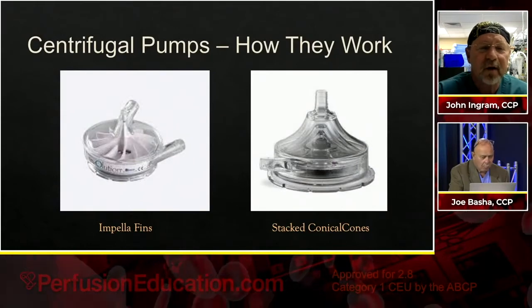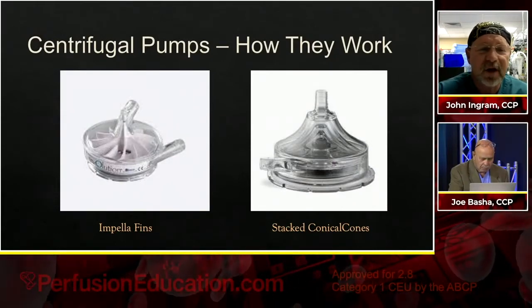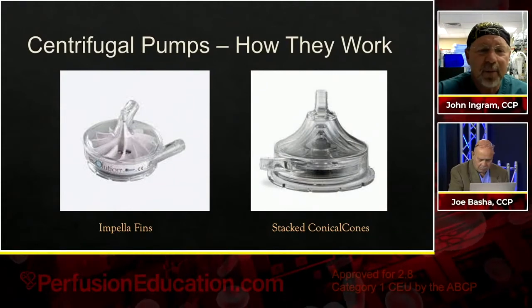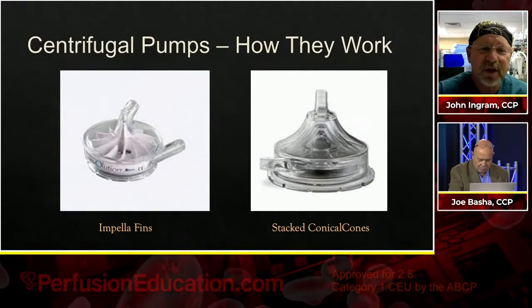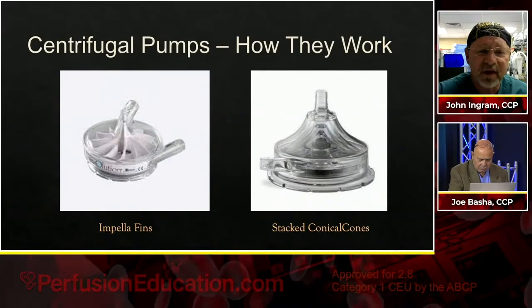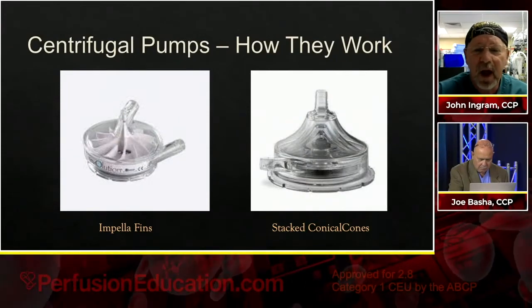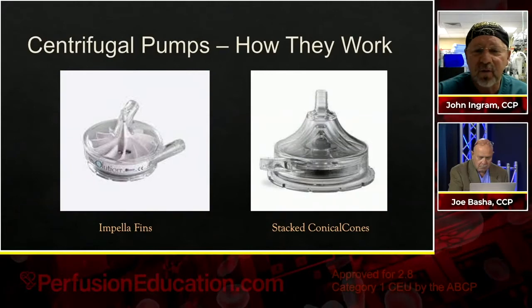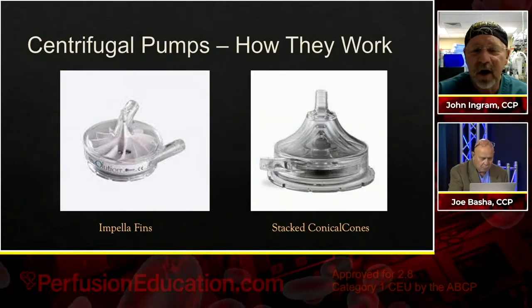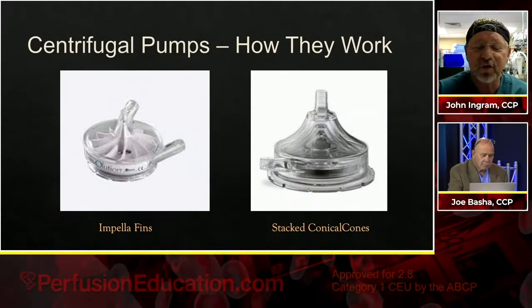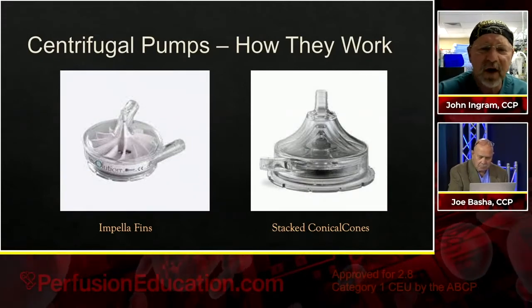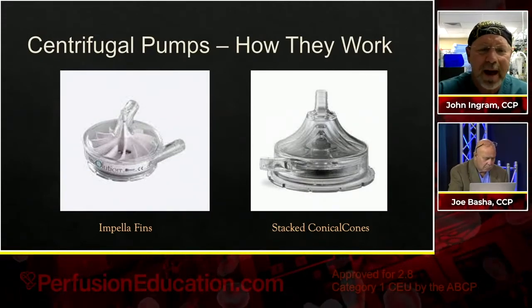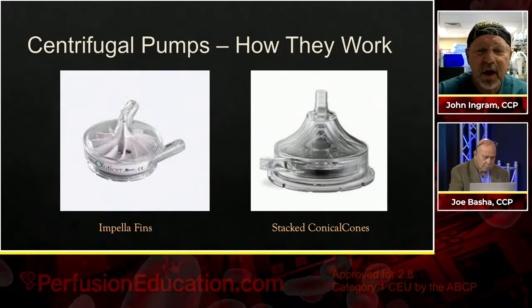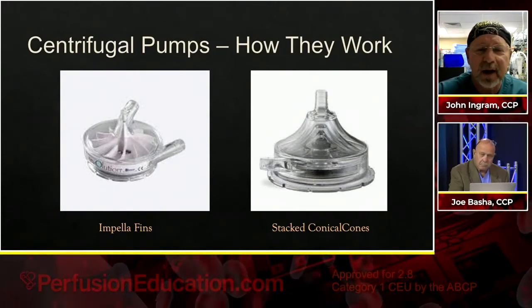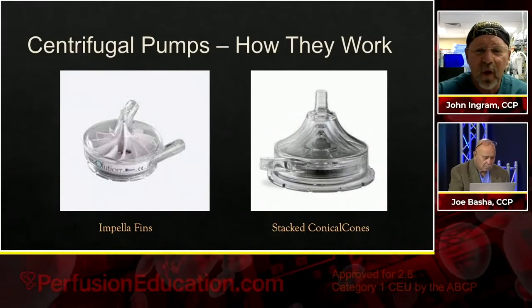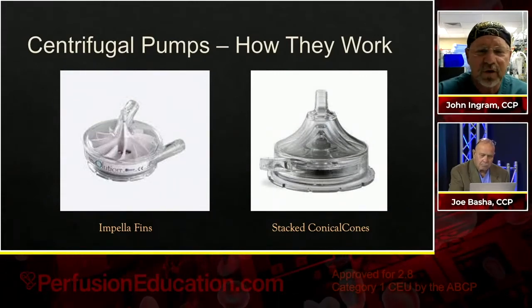So here's a couple diagrams. If you can see the inside mechanism of the pump on the left, this pump is basically using more of an impeller or fins to push the blood forward. And then the other on the right is really a series of stacked conical shaped cones generating a true centrifugal force. The advantage of the one on the left is that it would be able to run at a lower RPM because it's physically fan paddling the fluid forward, whereas the one on the right really relies on centrifugal force solely.